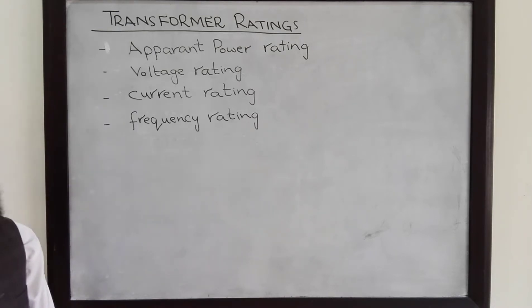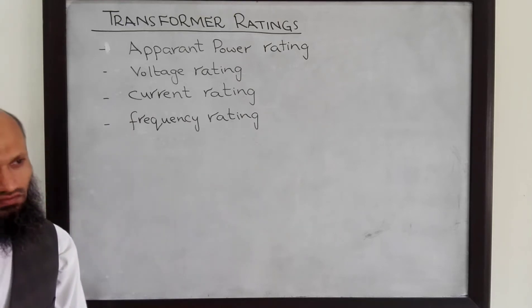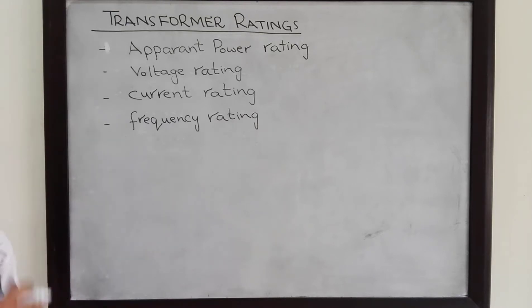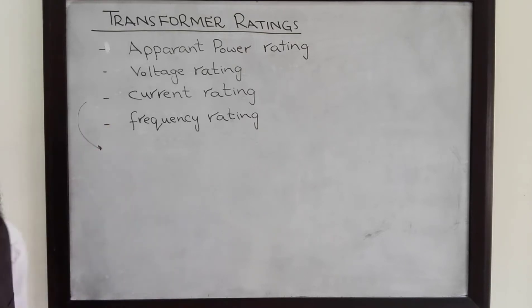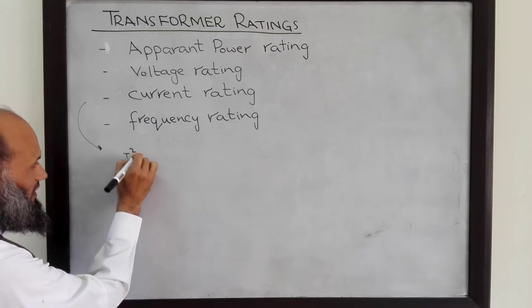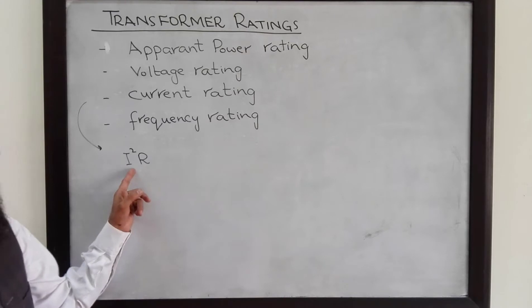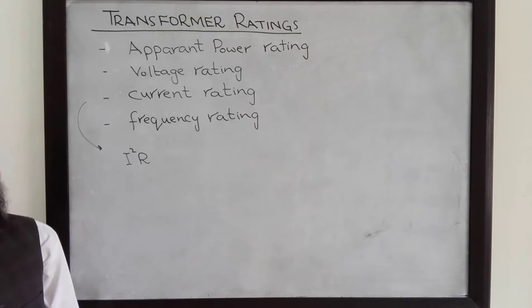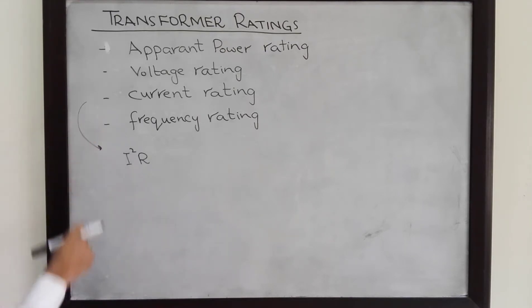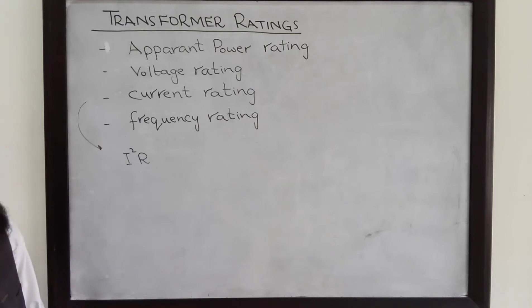The maximum current that the transformer can handle is described by these ratings. Basically, when current flows in the windings of the transformer, it produces heating in the transformer. There is a resistance of copper winding, and when current flows through the windings of the transformer, there are I²R losses. These losses are in the form of heat, and if there is excessive heating, that may melt down the windings of the transformer and thereby damage the transformer. Therefore, there is a limit on the maximum current that can be handled by the transformer, and this is described by the current ratings.